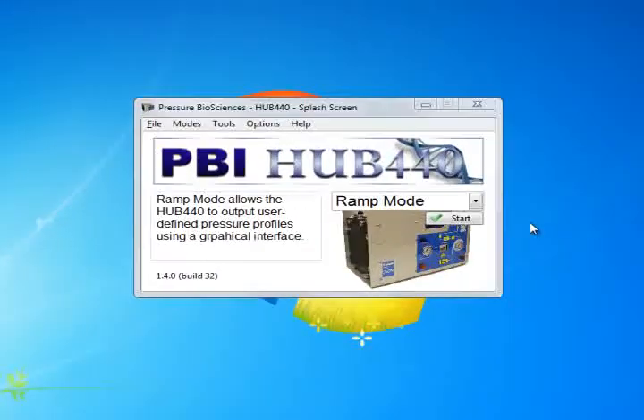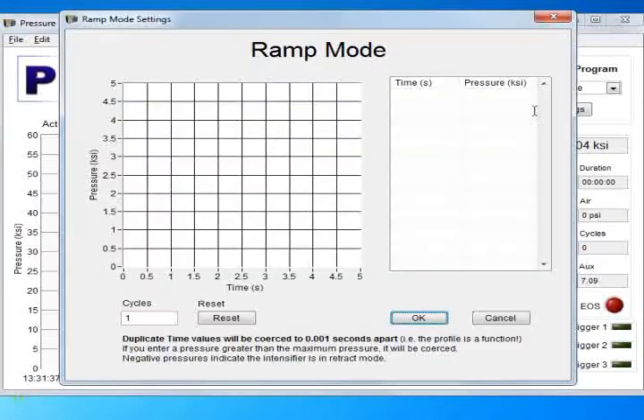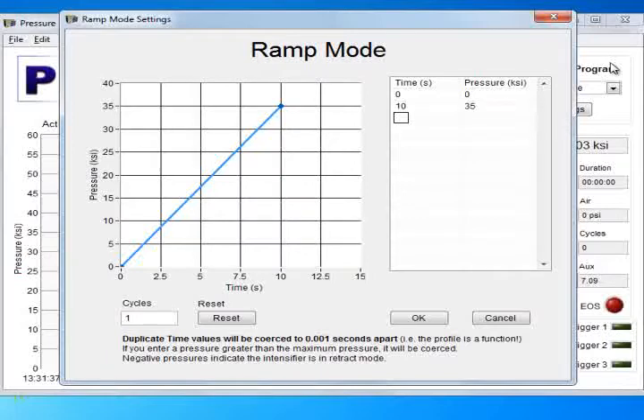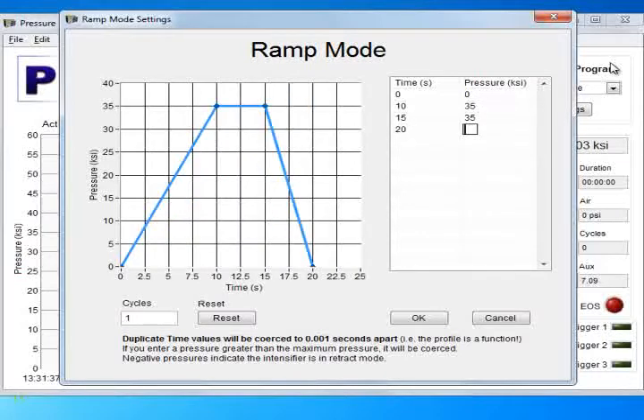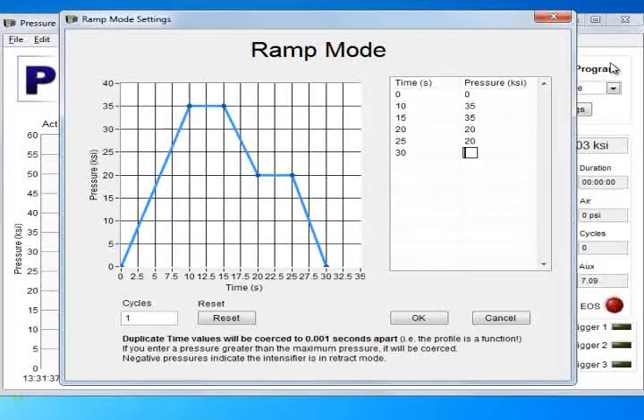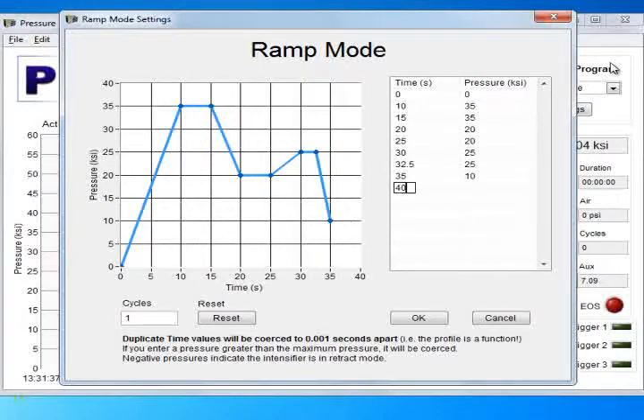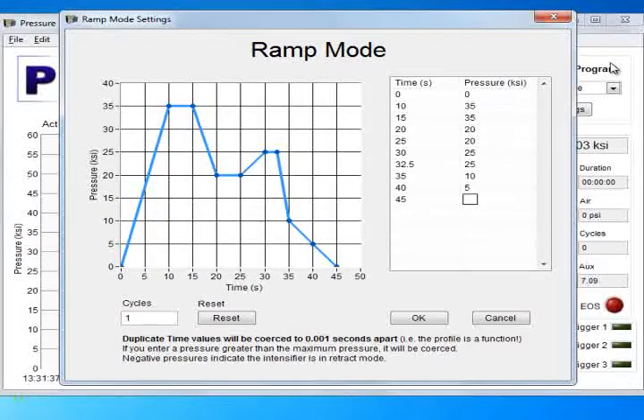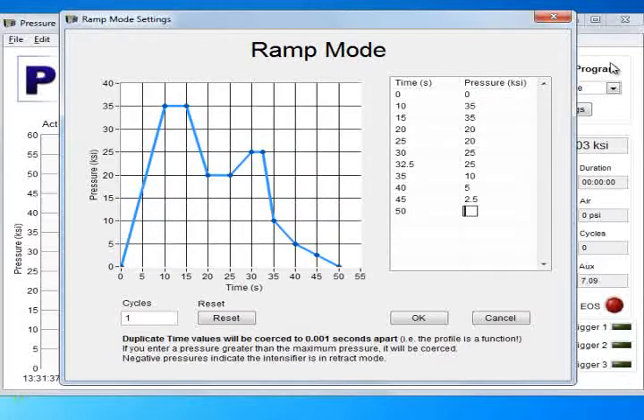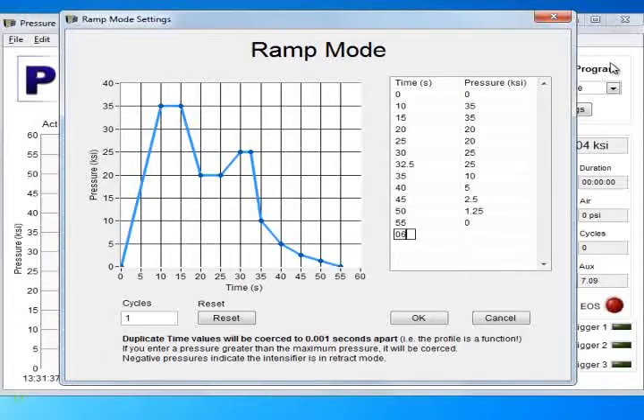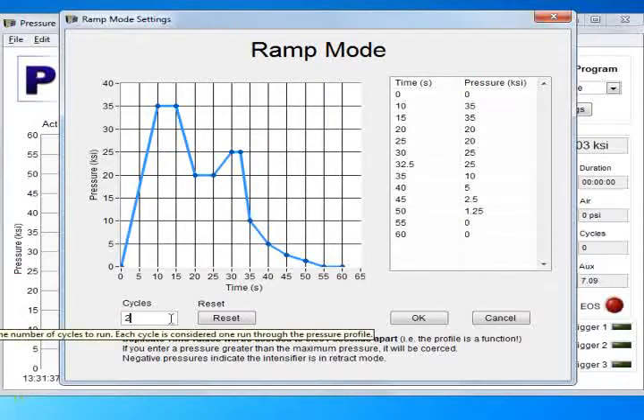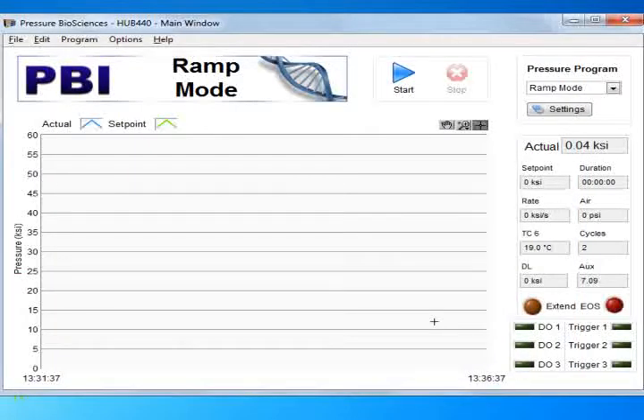The ramp mode allows very sophisticated control of pressure over time by employing the user program constructed on the fly from the table of time and pressure values imported from an Excel spreadsheet, comma delimited file, or entered by user. Programs and settings could be subsequently saved into a proprietary program setting file for the future experiments. As the data are being entered into the table, the program automatically interpolates the pressure values between the points. This allows the user to create very sophisticated programs including nonlinear changes of pressure over time, just like shown here.